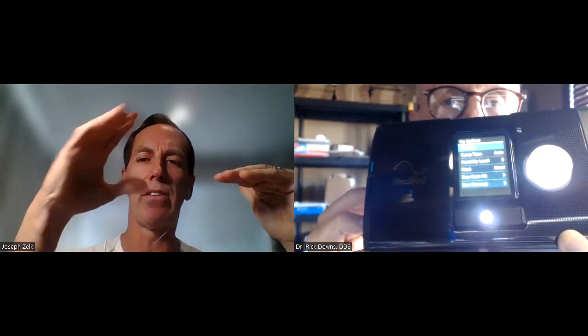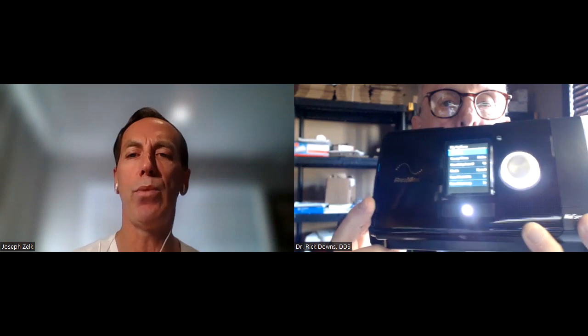And if it's flattened, it means you have airway restriction. So it's looking for a nice S wave there. And it'll incrementally increase that pressure, typically 0.2 centimeters of water pressure, and it'll gradually go up and down throughout the night, depending on what you need. It'll find your individual pressure, and it'll do that for every 3 breaths on average. And over a few weeks, we can find what your average pressure is, and it's going to look for your average or mean pressure and your 90% pressure.